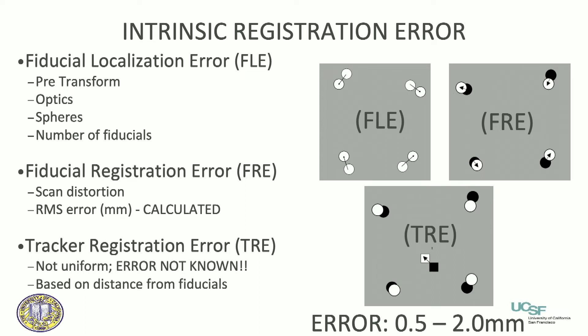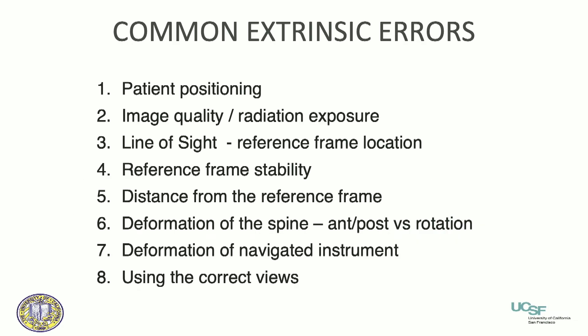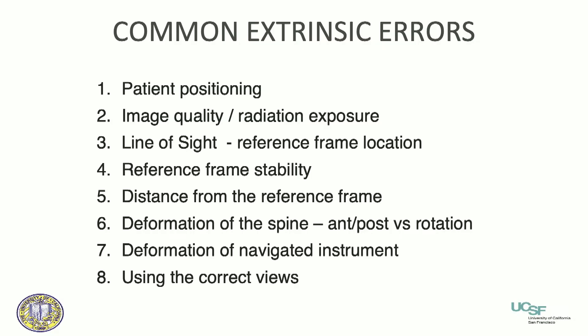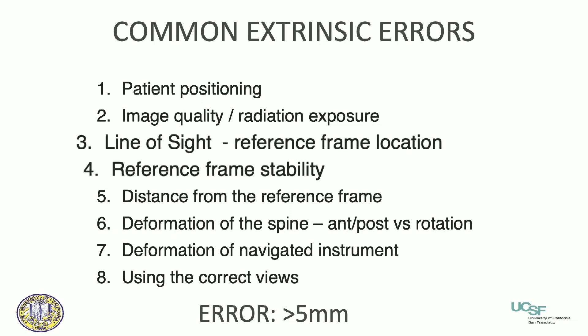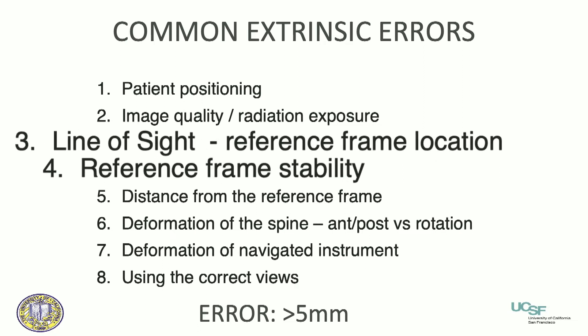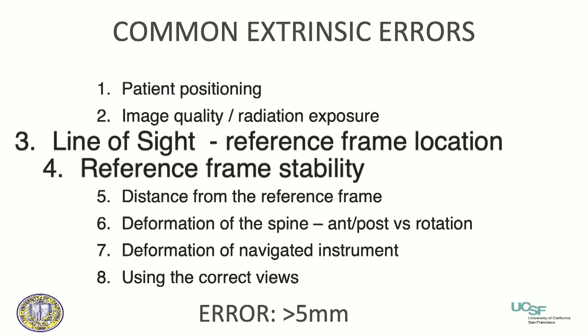Essentially it's small — between half a millimeter and two millimeters depending on the system. But where the errors really come in, it's us — it's the surgeons, the people using the tool who don't know how to use the tool. There are eight common errors that we make. Patient positioning, but the two big ones leading to larger errors are really line of sight — where you put the reference frame — and reference frame stability. If you put it in and don't secure it well, and it's in osteoporotic bone and the frame moves, the registration process goes off. And then guess who gets blamed? Not the surgeon — the system gets blamed, but it's actually the surgeon. We have to own the fact that when using navigation, we need to understand these common extrinsic errors.